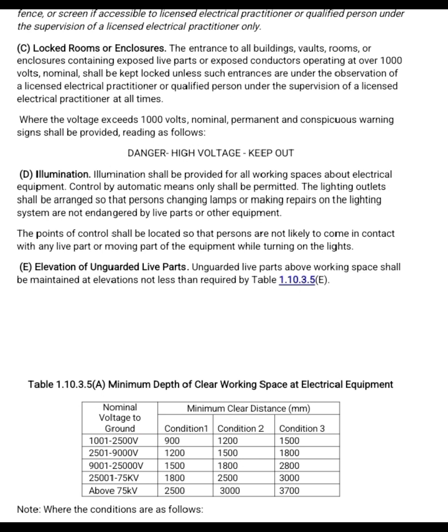Condition 3, 3700. This indicates that any room or enclosure that contains exposed live electrical parts with over 1000 volts must always be locked. It should only be opened when a licensed or qualified electrical practitioner is present. If the voltage is above 1000 volts, a warning sign must be posted. Illumination: areas where electrical work is done must have proper lighting. Lights should be controlled automatically, with no manual switches near danger.